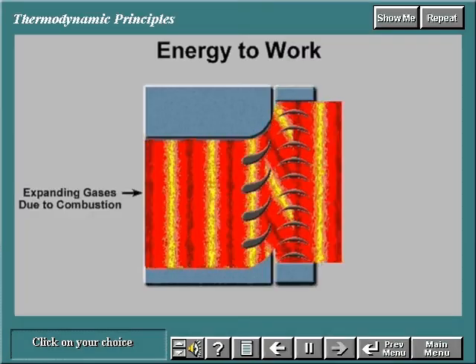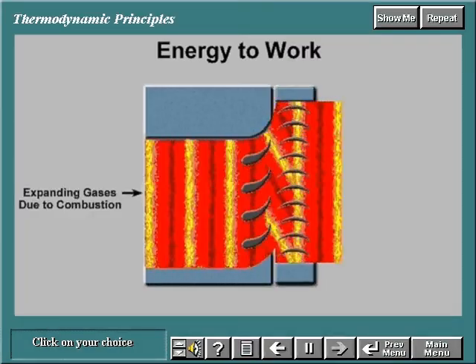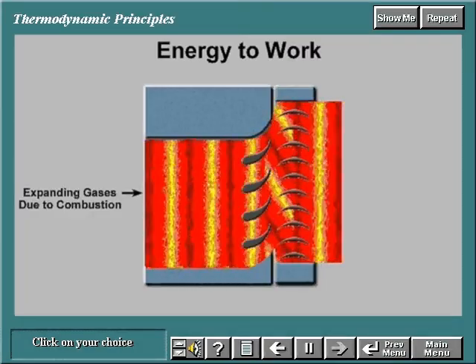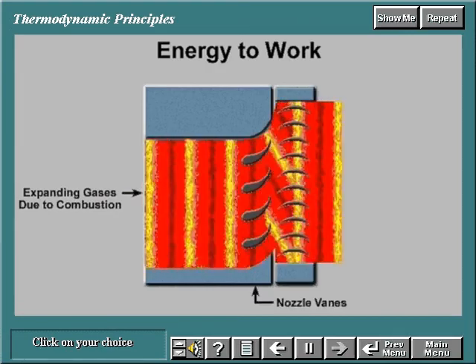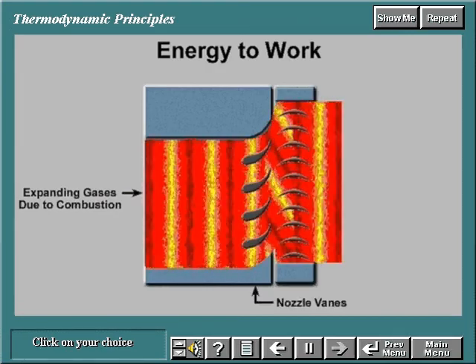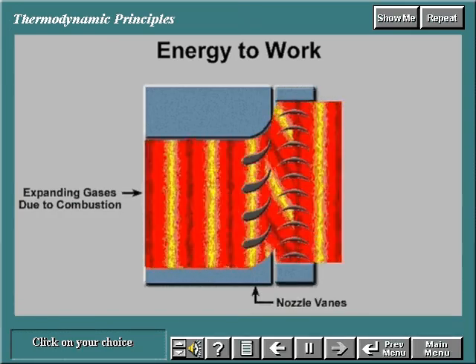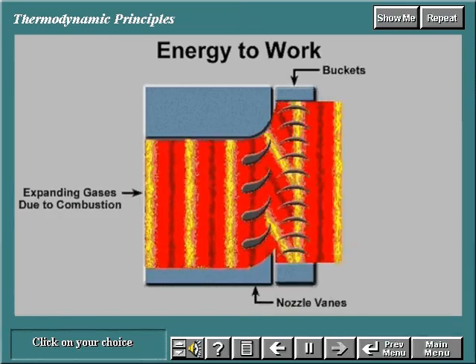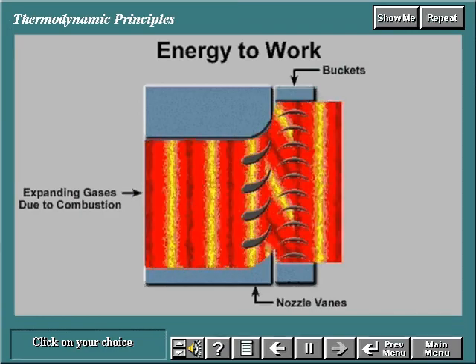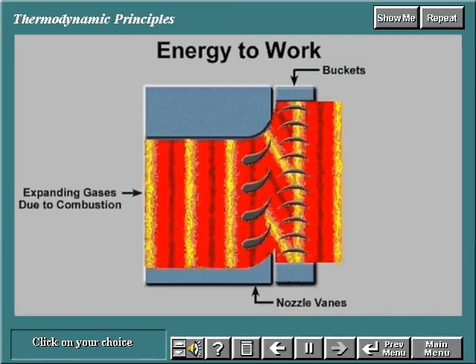The conversion of work in either turbine actually takes place in two steps. In the nozzle section, the hot gases are expanded and a portion of the thermal energy is converted into kinetic energy. In the subsequent bucket section, a portion of the kinetic energy is transferred to the rotating buckets and converted to work.